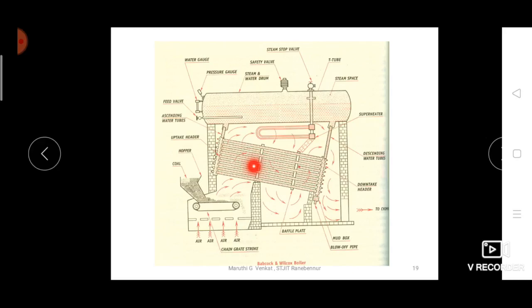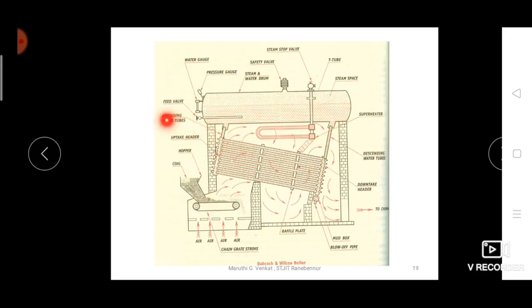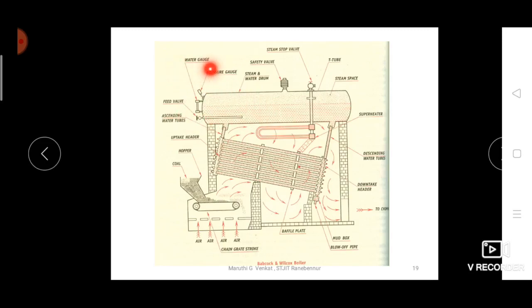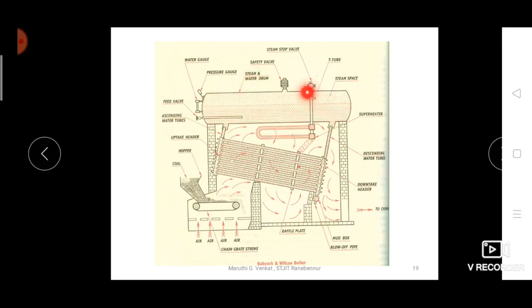There is a hopper part which contains the fuel — that is coal — and a grate part over which the fuel will be burnt to produce hot flue gases. Ascending tubes connect the boiler to the uptake header tube, and descending tubes connect the boiler to the downtake header tube. The feed valve feeds water inside the boiler. The water gauge measures the water level, and the pressure gauge measures the steam pressure inside the boiler.